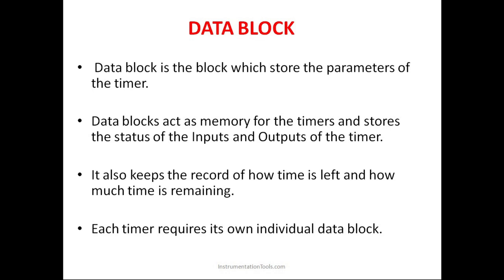Whenever you take a timer in TIA Portal, it will automatically create one data block in which it stores the status of the timer. Data blocks act as memory for the timer — storing the on and off state of inputs and outputs, as well as the time which has been completed. Each and every detail of the timer is stored in its own data block, including how much time is left. Each timer has its own individual instance data block.